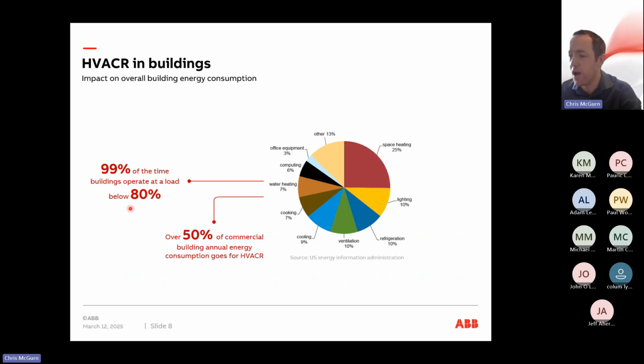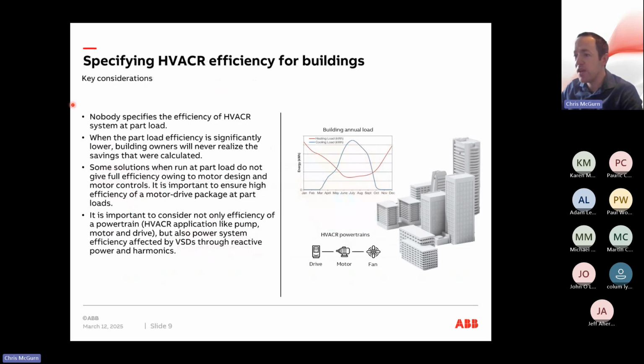And if you're running below that load, it can have an impact on efficiency. So nobody specifies the efficiency of HVAC/R systems at part load. And when the part load efficiency is significantly lower, building owners never realize the savings that were calculated. So again, you need to consider your system as a whole. When you're considering your fan, your motor, your drive, your complete system should be considered, and you should understand what speeds, what loads your fan needs to be running at, so that you can maintain a proper control over your HVAC system.